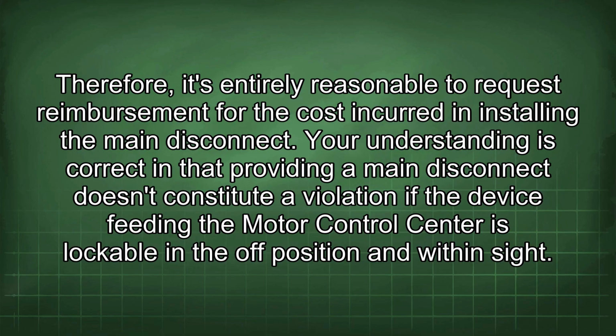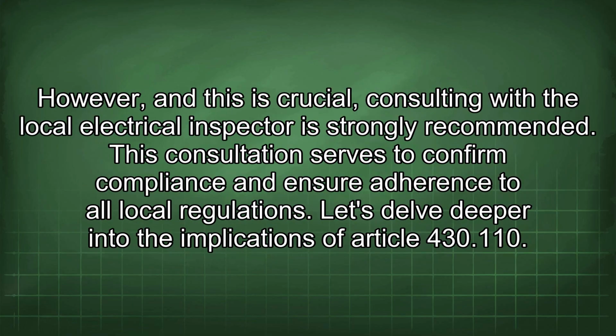Your understanding is correct in that providing a main disconnect doesn't constitute a violation if the device feeding the motor control center is lockable in the off position and within sight. However, and this is crucial, consulting with the local electrical inspector is strongly recommended. This consultation serves to confirm compliance and ensure adherence to all local regulations.